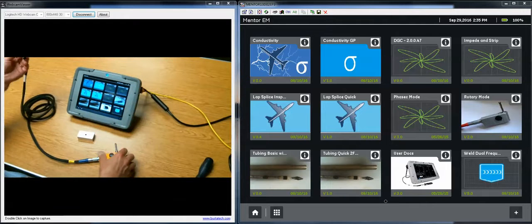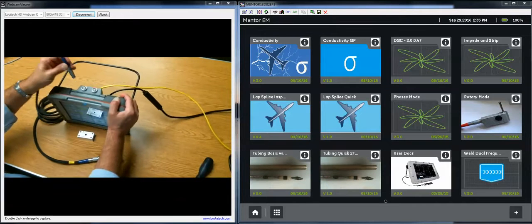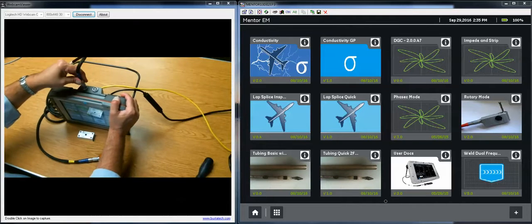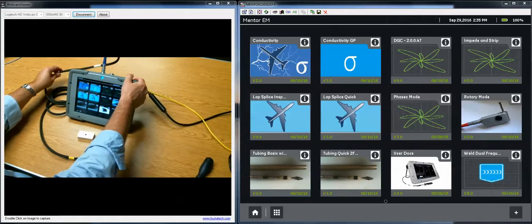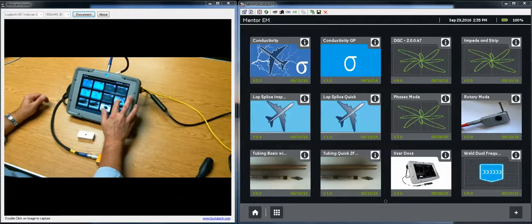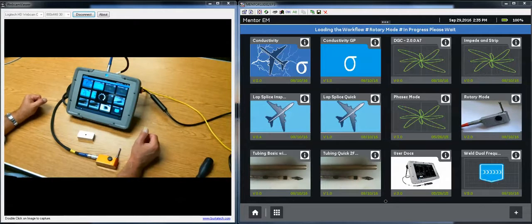Now we have added some special features to the Mentor EM to control the speed of the drive and to start and stop the scan very easily with the button on the drive unit. The drive unit comes with its own cable. That plugs into input 1 of the Mentor, and we use the Rotary mode app.